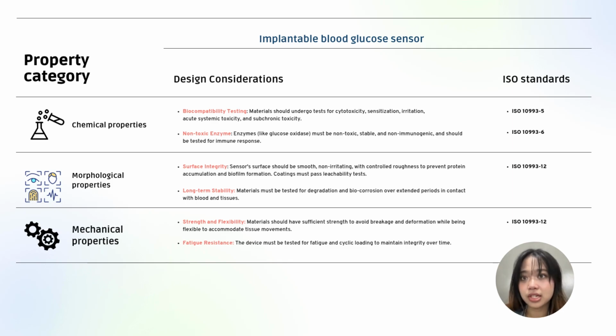So the next category is morphological properties. The design considerations are, first, surface integrity. The sensor surface should be smooth and non-irritating, with controlled roughness to prevent protein accumulation and biofilm formation. Coatings must pass the leachability test. It is from ISO 10993-12. So next, the long-term stability. Materials must be tested for degradation and biocorrosion over extended periods in contact with blood and tissues. It is based on the same ISO standard, ISO 10993-12.